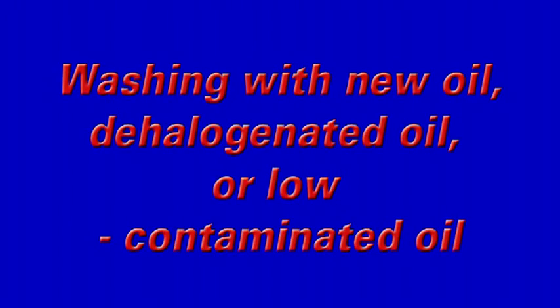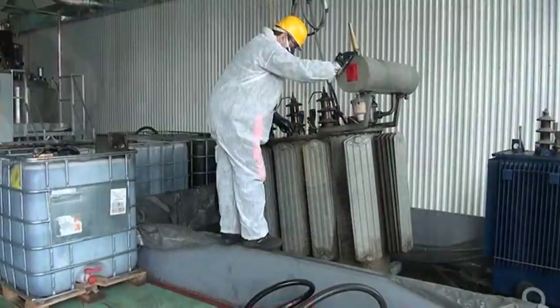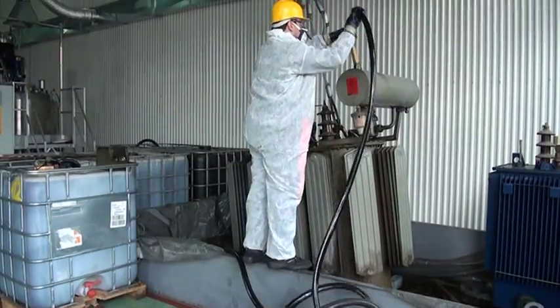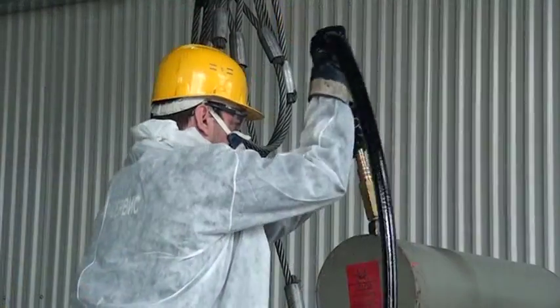Washing with new oil, dehalogenated oil, or low contaminated oil. The transformer's carcasses to be washed must be filled with new oil, dehalogenated oil, or low contaminated oil, preferably hot, at 70 degrees Celsius.